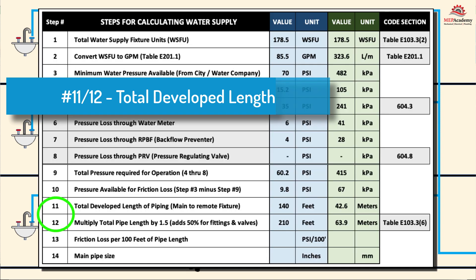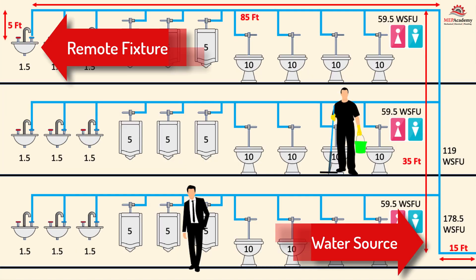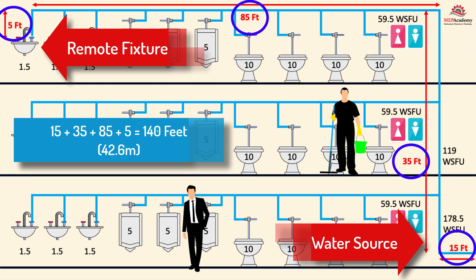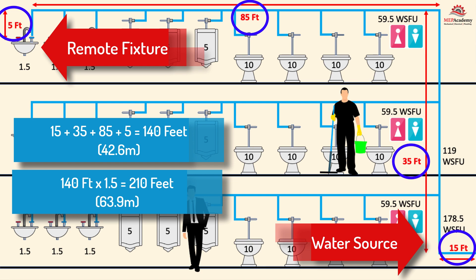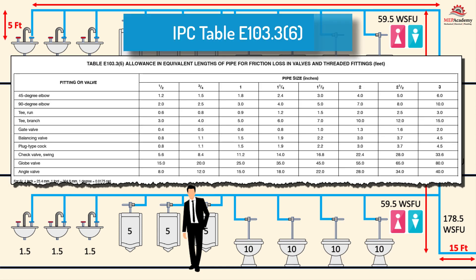Steps 11 and 12: Total Developed Length of Piping. This is the developed length of water piping from the water source to the most remote fixture, multiplied by 1.5 to account for pressure lost through fittings and valves, which add approximately 50% to the total length. In our example, there is a total of 140 feet (42.6 meters) from the source to the most remote fixture: 140 × 1.5 = 210 feet, or 42.6 × 1.5 = 63.9 meters of total developed length. If the exact number of fittings and valves is known, IPC Table E103.3.6 can be used to determine the equivalent length for each size and type.